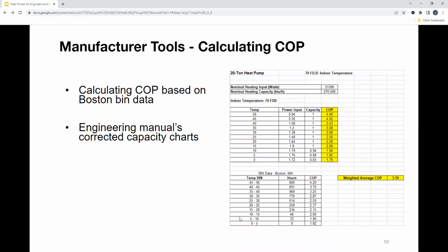And then already this has been built in, has your bin data. So between 50 and 45 degrees, we spend about 689 hours at that temperature, right? So you can kind of go through, look at the hours spent, and then come up with an overall weighted average. So what you're able to do is go into the engineering manual, take the input rating, take the percentage of capacity that you get, enter all this into the power input and capacity, and then you can see your COPs at certain temperatures. And they're a little bit different for each heat pump depending on the size, but this is a general way to do that if you are trying to understand COP at a different temperature than your 47 and 17 degrees.